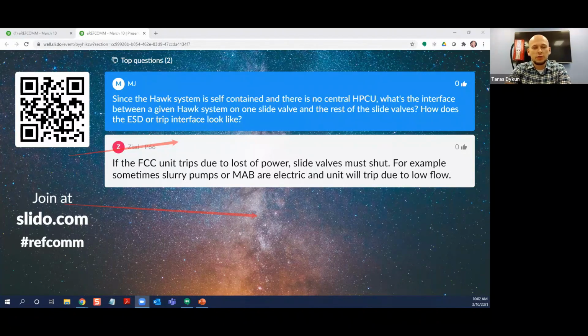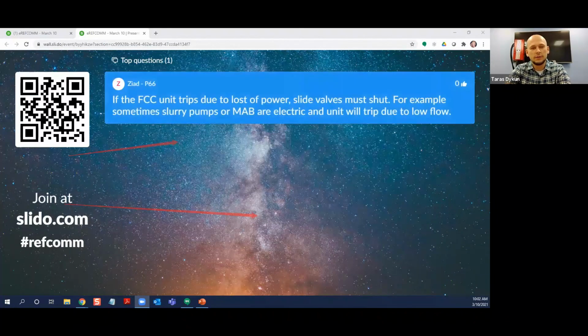So if the FCC unit trips due to loss of power, the slide valve must shut. For example, sometimes slurry pumps or MAB are electric and the unit will trip due to low flow. Well, if your FCCU requires the valve to shut on loss of power, we would use the accumulator system, which opens the solenoid valve and dumps all the fluid into one side of the cylinder to make sure the valve is shut. So it works the same way as an ESD system on these units.